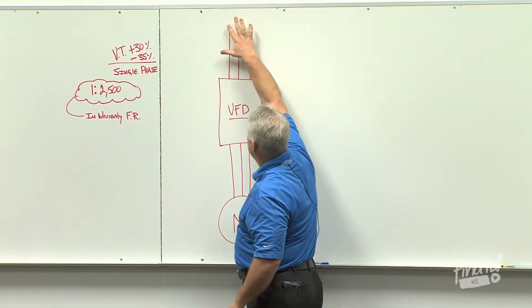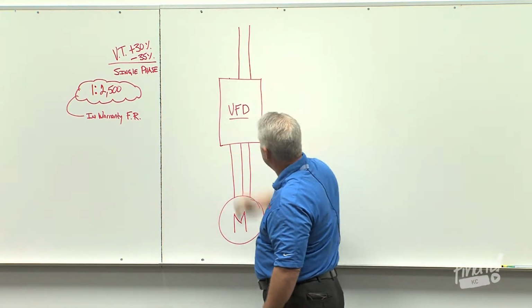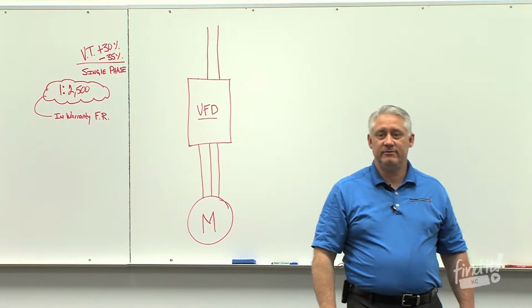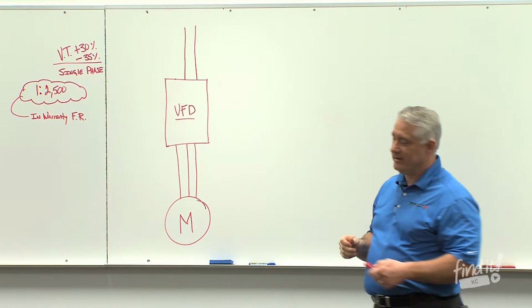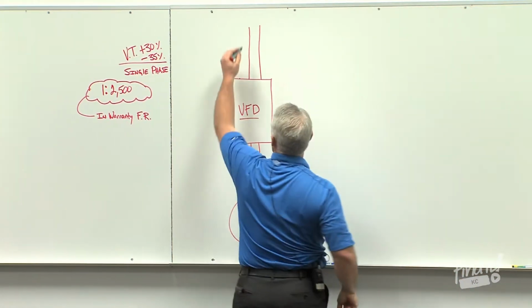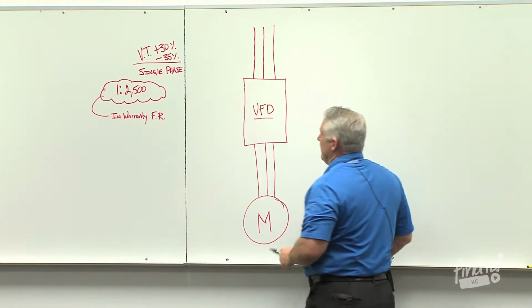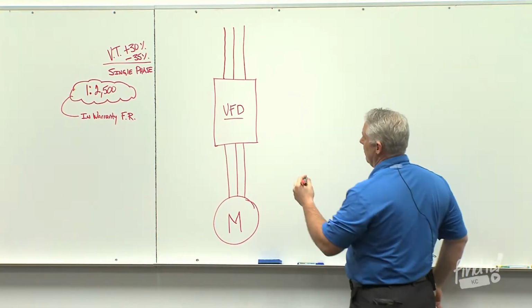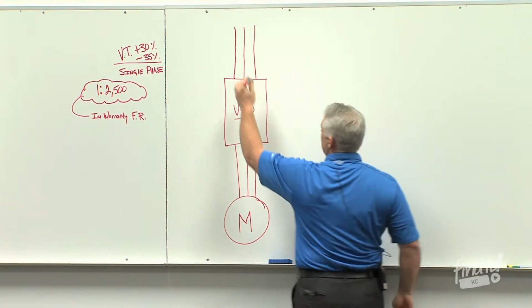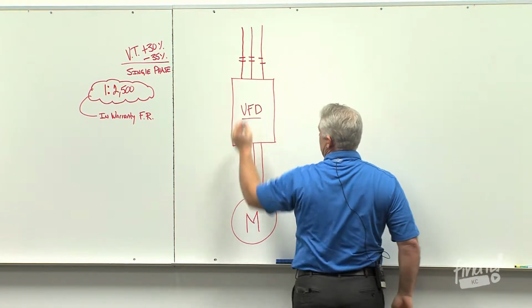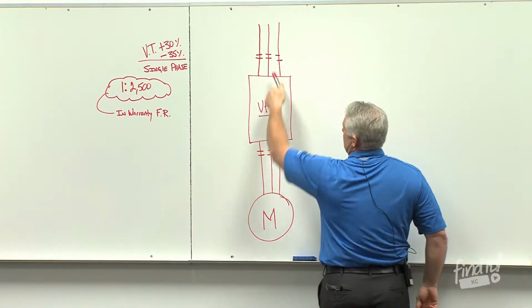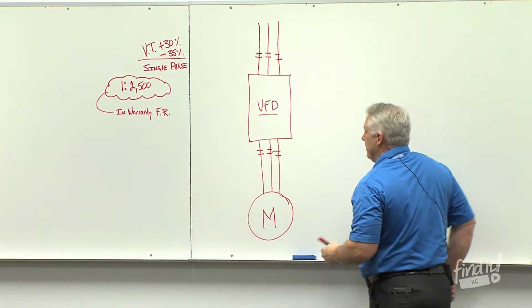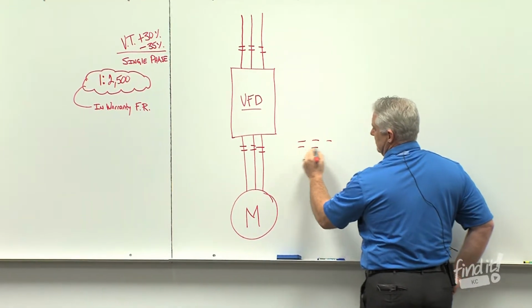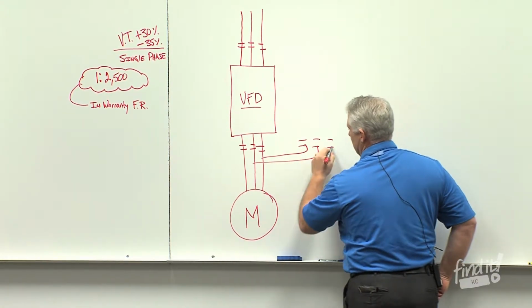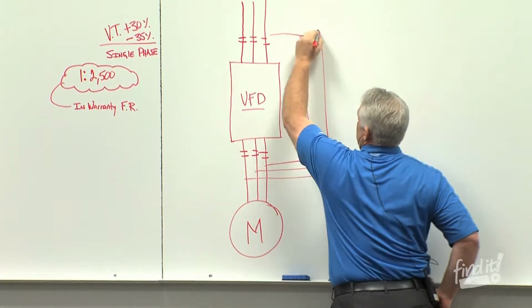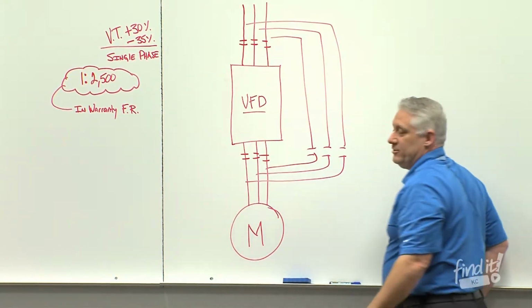We also, as Richard talked about, can lose a phase and still operate the motor, amazingly enough, without a bypass. If we had a bypass, it's a different story. We'll go into that in a minute. So add that phase back in there. So what is a bypass? A bypass is, like I said, we're going to route power around. So back in the 80s, we came up with this really crude practice of what's called a three-contactor bypass. There's a drive isolation contactor, a VFD output contactor, and then what's called your bypass contactor. What we're doing essentially, as I said before, is routing power around the VFD in case of an emergency.